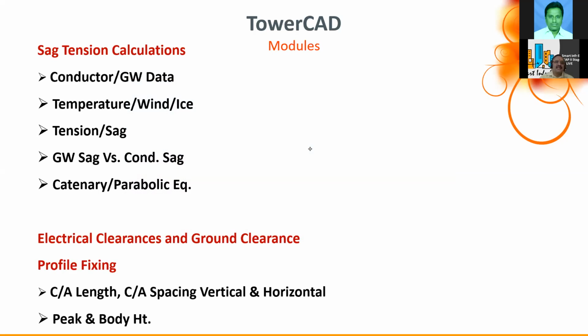These are the sag tension calculations, done as per the conductor and ground wire data, considering temperature, wind, ice, tension and sag. We consider ground wire sag versus conductor sag, using the catenary parabolic equation and cubic spline to solve sag and tensions. Electrical clearances are required to check cross arm length, cross arm spacing vertical and horizontal, and the peak height or body height.